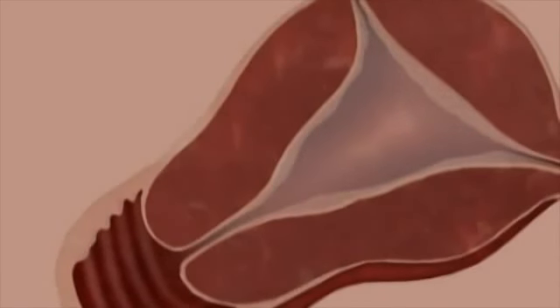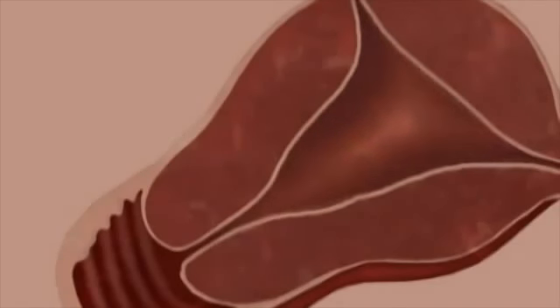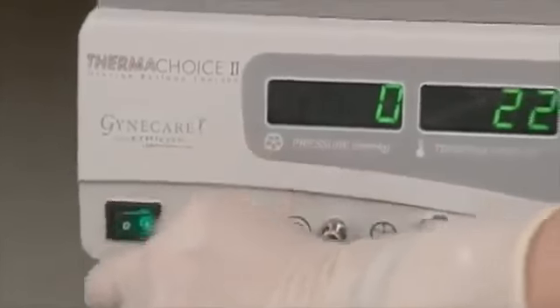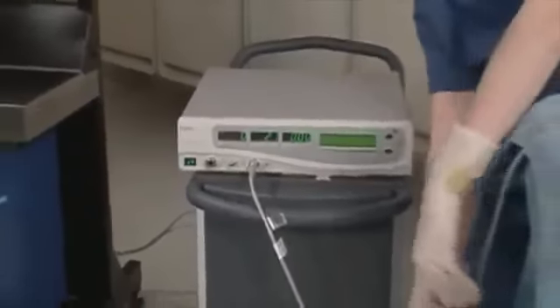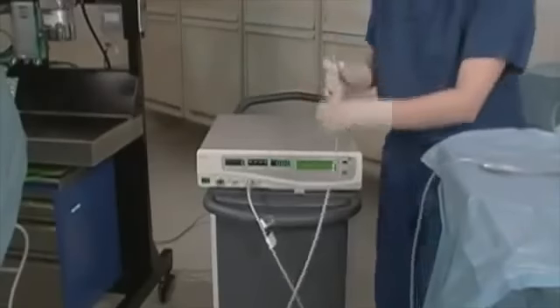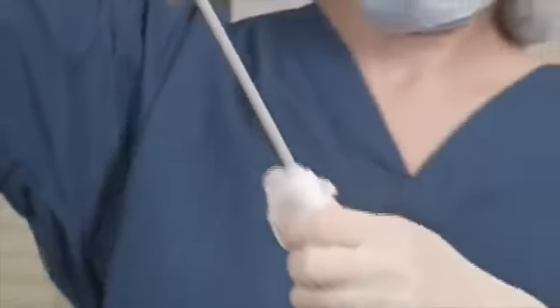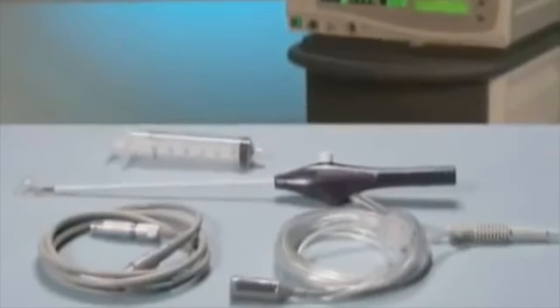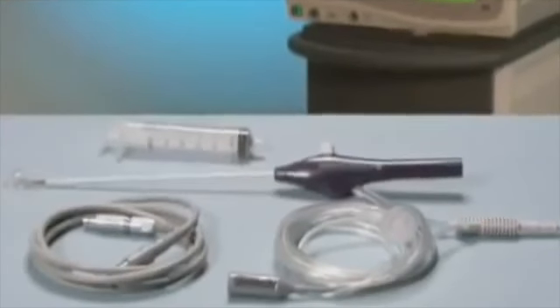Ablation occurs via thermal necrosis or destruction of the endometrium into the superficial myometrium. This necrotic tissue is sloughed off, much like the uterine lining is sloughed off during menses, usually causing a significant reduction or complete elimination of menstruation. After the catheter has been removed, the pressure line and circulation plug are disconnected from the controller. The umbilical cable and catheter are disconnected from each other, and the cable is disconnected from the unit and disinfected for the next case. Once this is done, the catheter is discarded. This concludes the in-service demonstration for the Gynecare ThermaChoice II Uterine Balloon Therapy System.